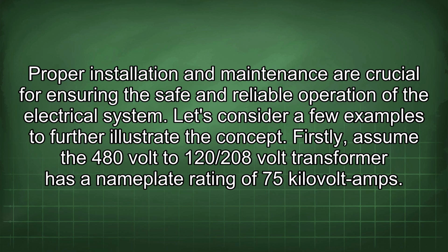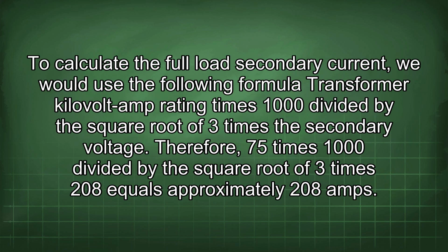Firstly, assume the 480 volt to 120/208 volt transformer has a nameplate rating of 75 kilovolt amps. To calculate the full load secondary current, we would use the following formula: transformer kilovolt amp rating times 1000 divided by the square root of 3 times the secondary voltage. Therefore, 75 times 1000 divided by the square root of 3 times 208 equals approximately 208 amps.